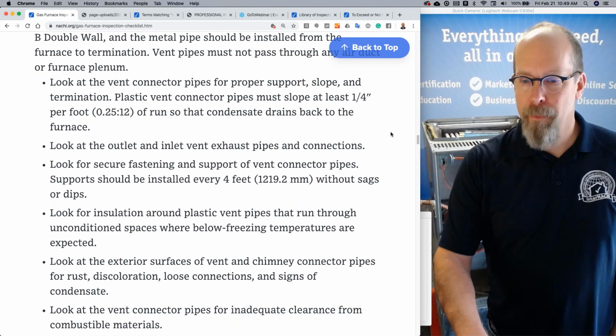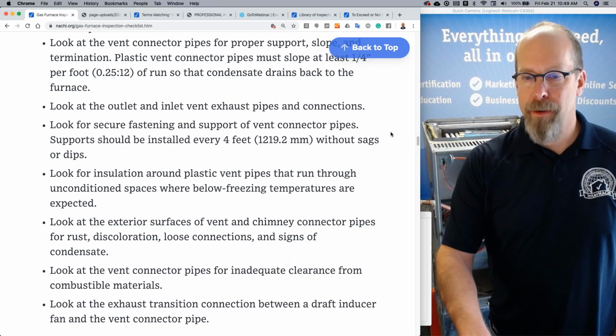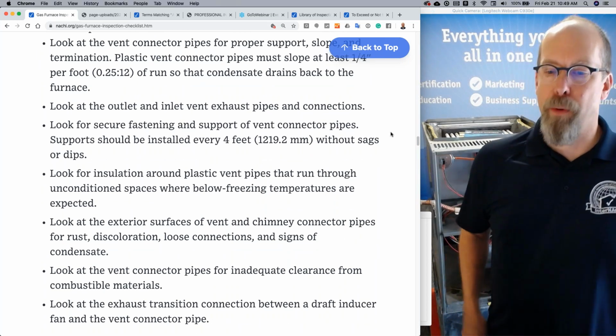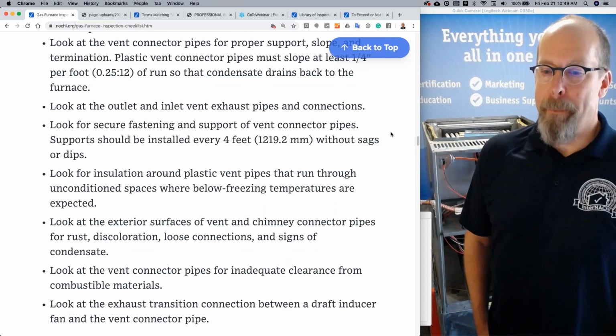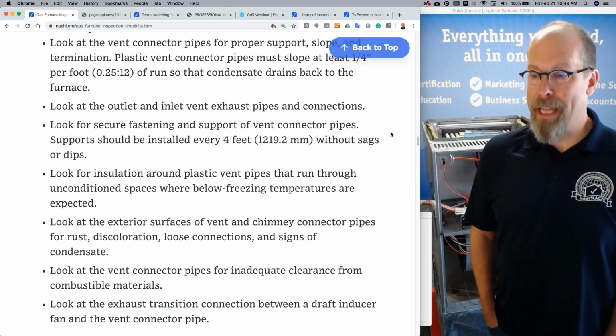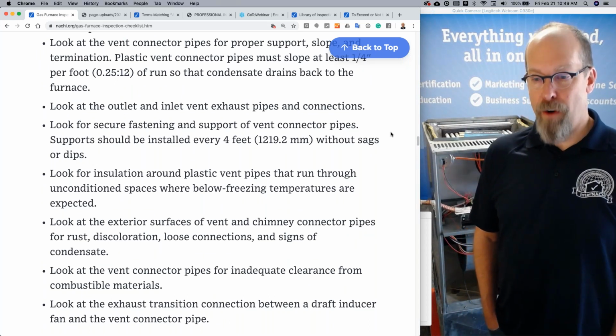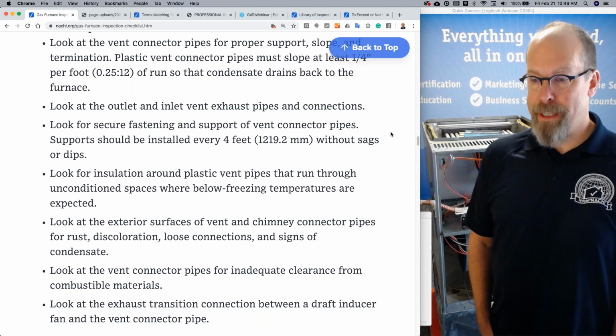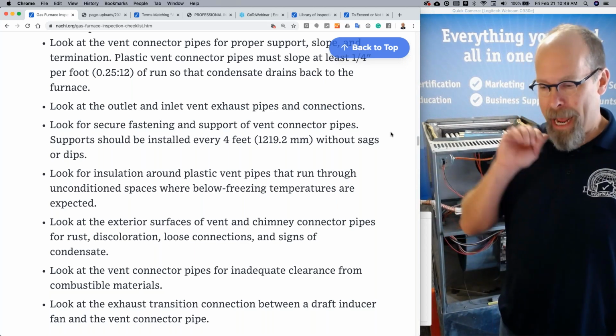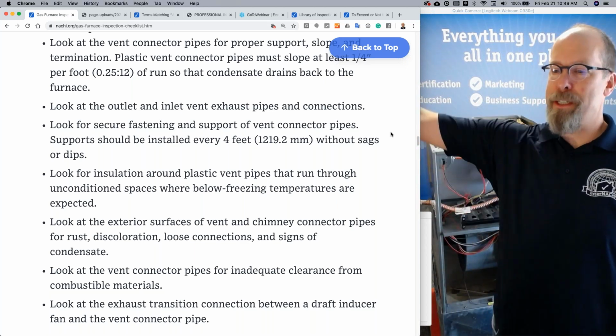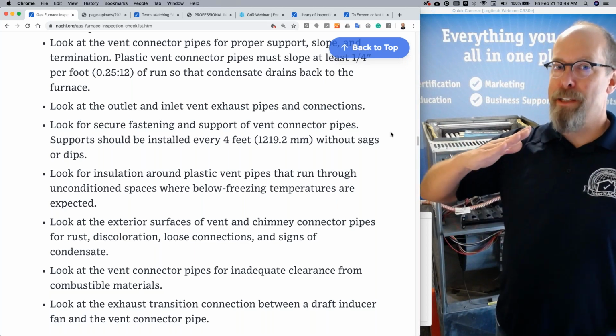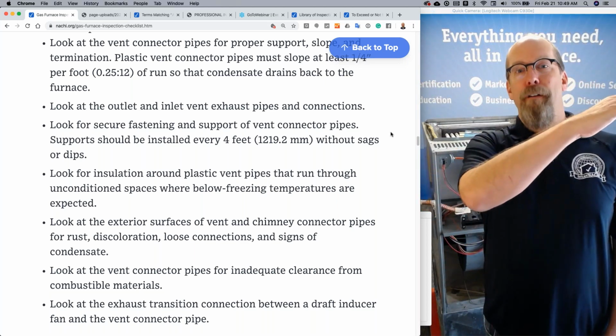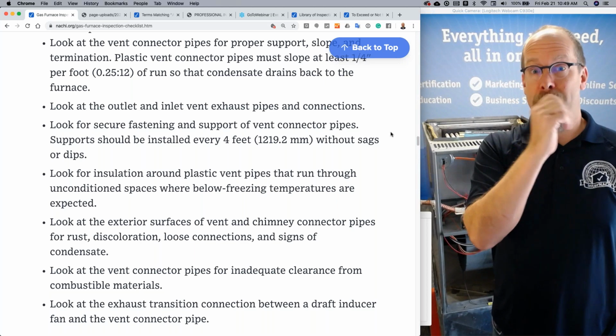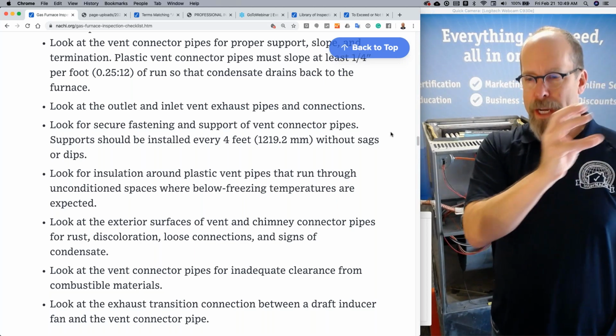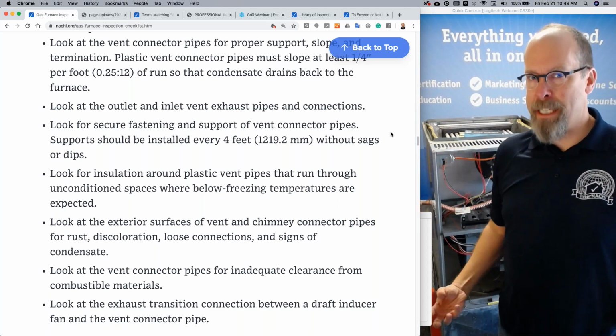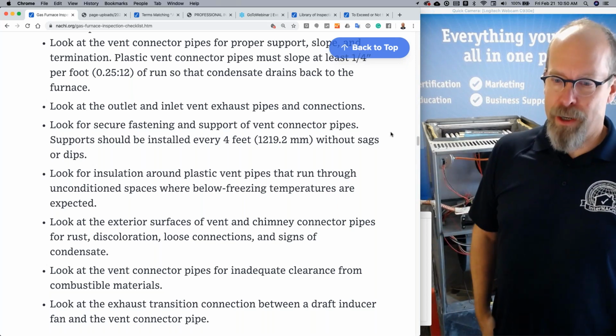So what do you do as a home inspector? Well, here's your little checklist. Look at the vent connector pipes for proper support and slope and termination. Plastic vent connector pipes must slope at least 1/4 inch per foot of run so that condensate drains back to the furnace. It doesn't drain out to the outside. It actually drains back to the furnace. It's sloped uphill from the furnace to the termination so that condensate, when it's produced, drains back to the furnace, is collected and discharged outside in a controlled manner.